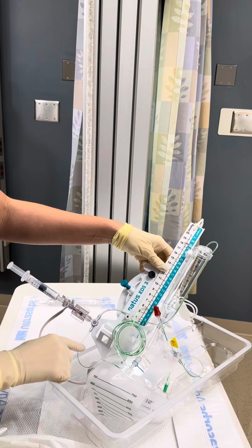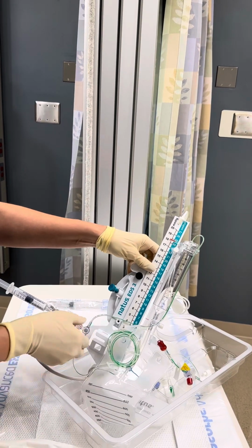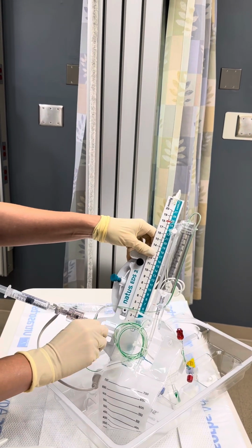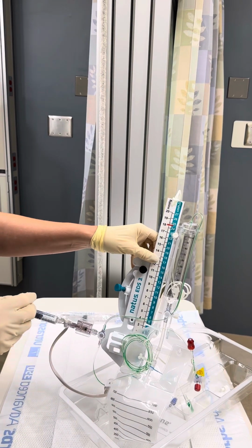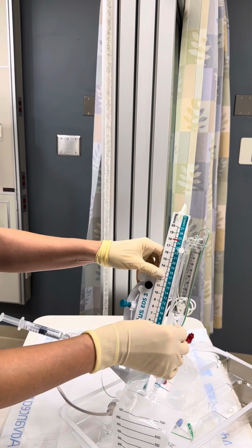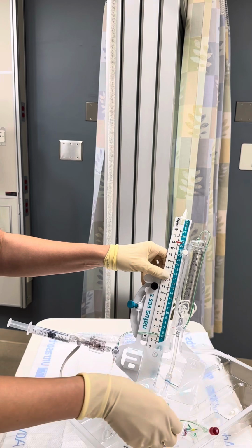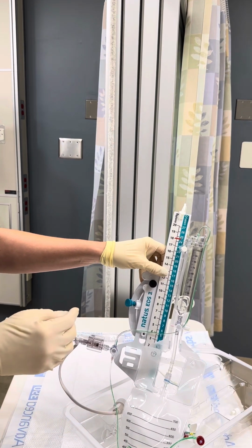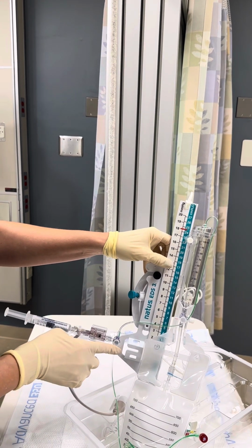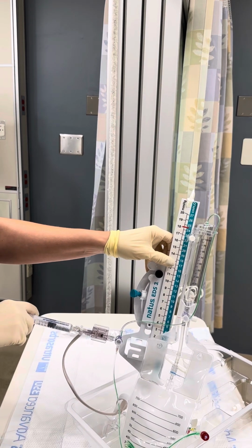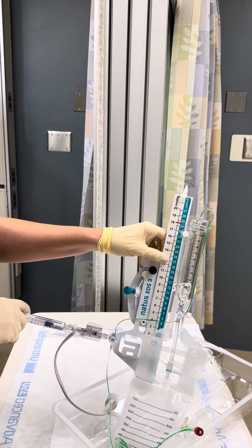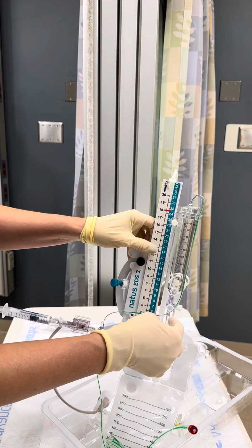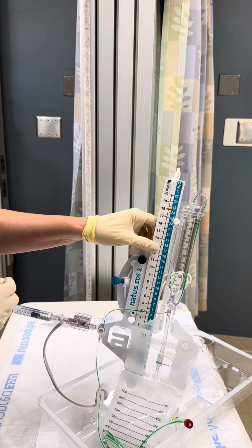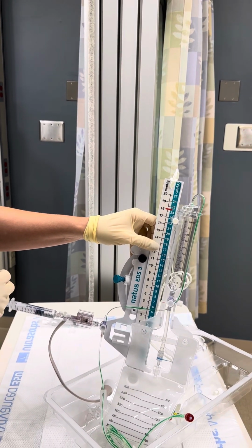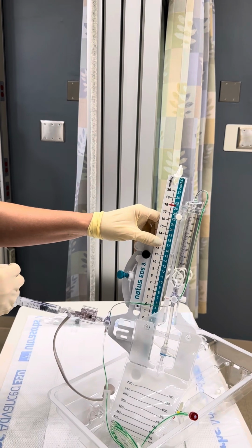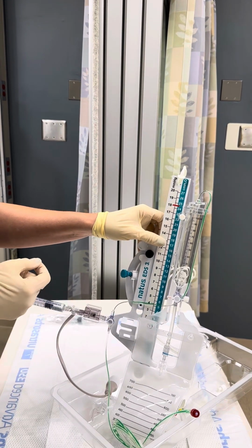Down is to the patient, so we're going to turn the stopcock down. Turn the stopcock off to the patient and inject saline until it is observed in the drip chamber. The stopcock is off to the patient, so we're going to flush to prime the line to the drip chamber. You see a little bit of fluid running in there. Also verify that fluid flows from the drip chamber into the collection bag. We saw that, so we're good there.